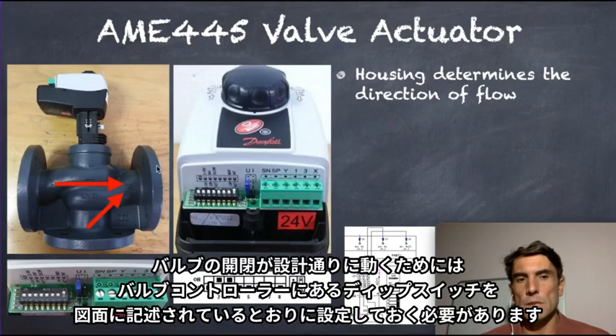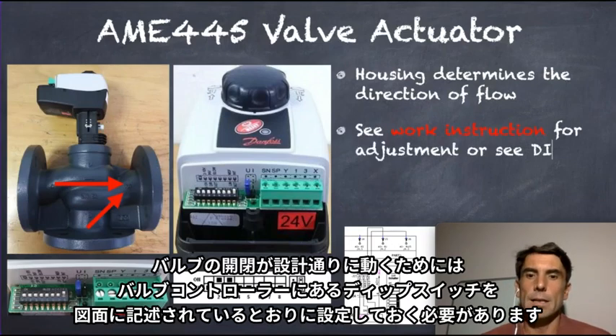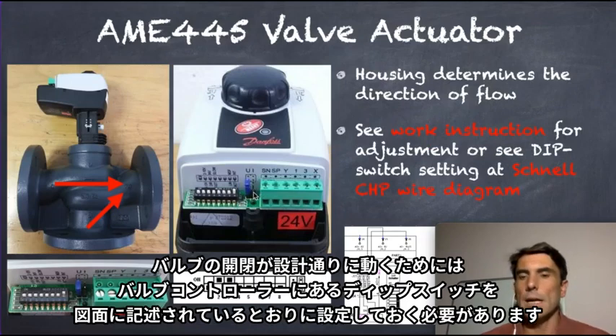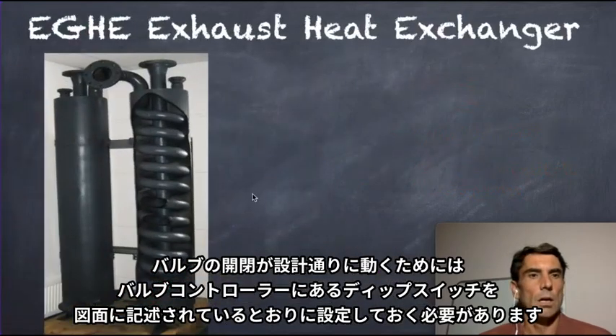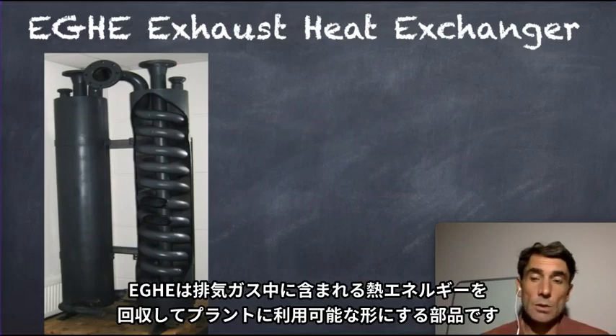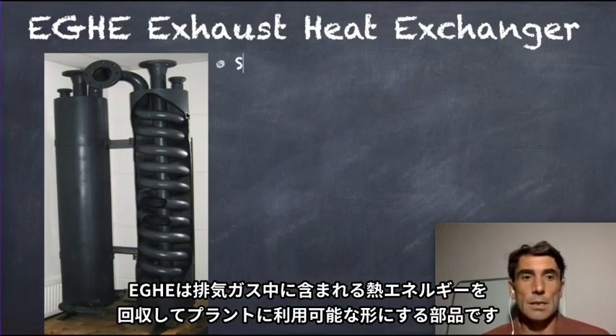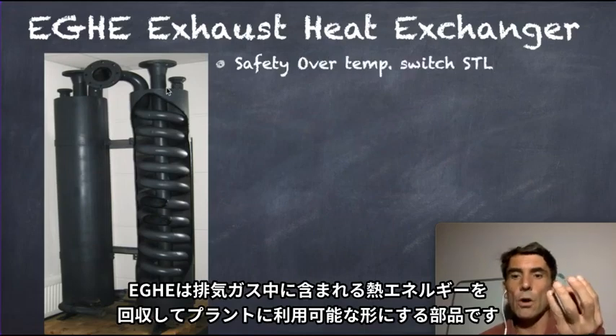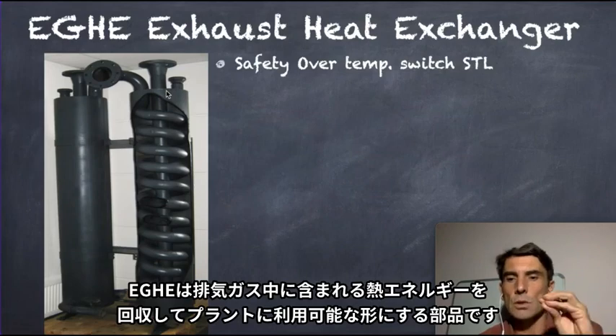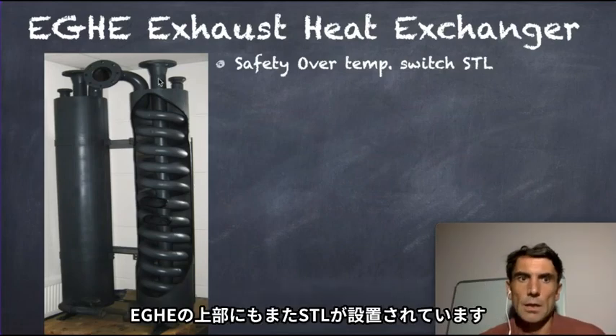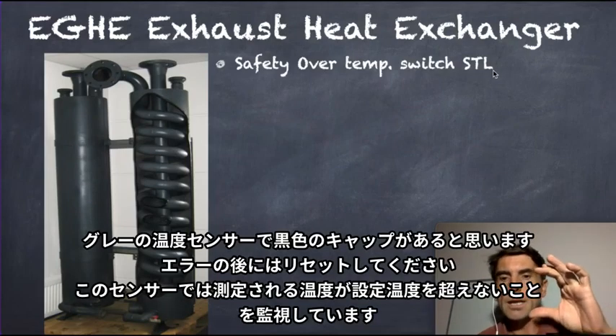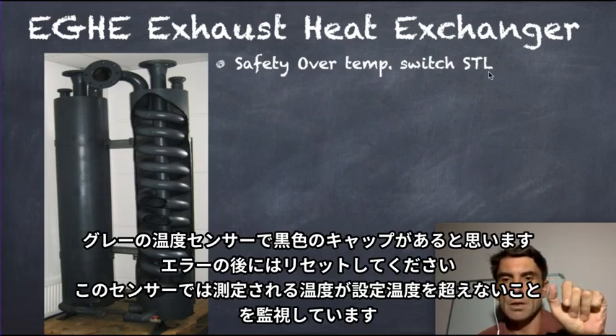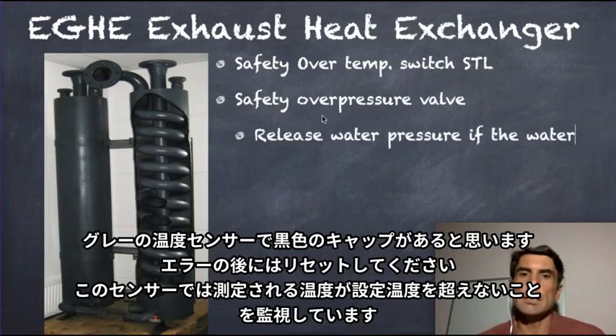Important is that we have the right position, so the mounting, so that the flow rate is right. The other thing, again, we have to keep an eye on how the dip switches and bridges are connected. Our exhaust gas heat exchanger is built to remove or to use the rest of the heat from the exhaust for supplying to the client. On top of the safety on the exhaust gas heat exchanger, we will find a safety temperature switch. Again, there's a gray temperature switch with the red-black cap, where we have to reset. The important thing here as well is that we do not exceed the limit.